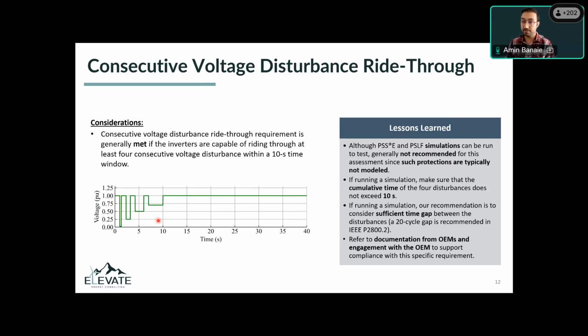So one important factor about this is that although PSSE and PSLF simulations can be run for this test, and that's what we do as well, it's not generally recommended, since this consecutive voltage disturbance ride-through functionality is not typically modeled in phasor-based software or even in EMT software. So you want to reach out to the OEM to make sure if that's implemented or not. And if running a simulation, you want to make sure that these 4 disturbances remain within the 10-second time window that PRC-29 has, and also allow sufficient time gap in between each voltage disturbance to have a realistic simulation scenario. IEEE 2800.2 recommends a 20 cycle gap for this specific requirement as an example. And then make sure to refer to the documents to see if your simulation results make sense.